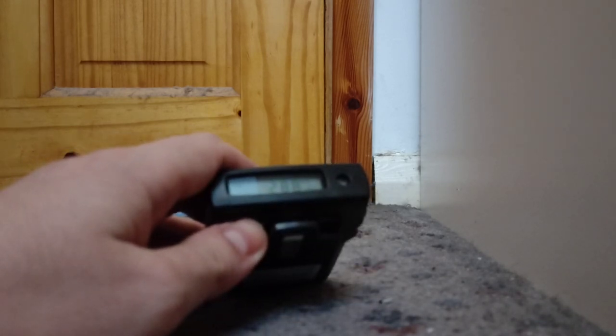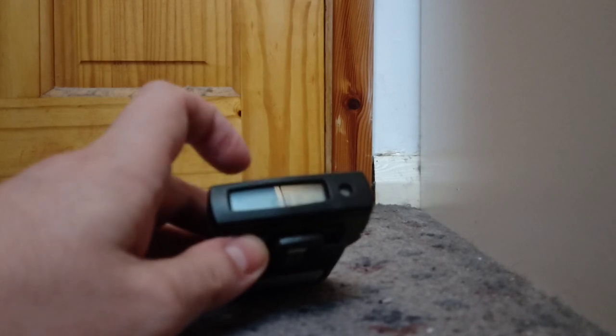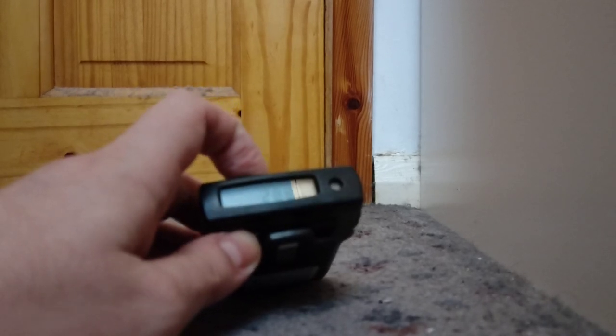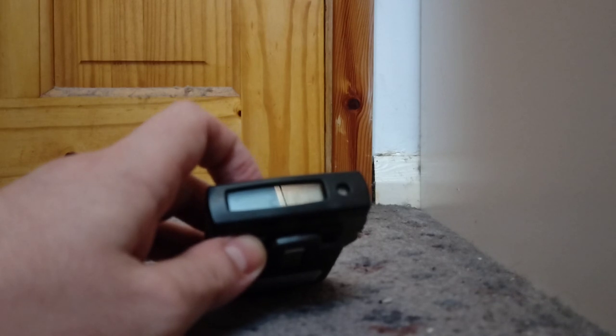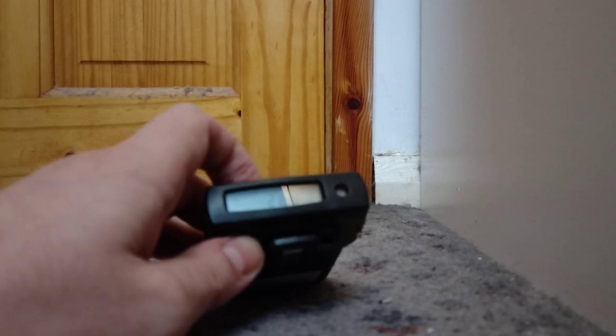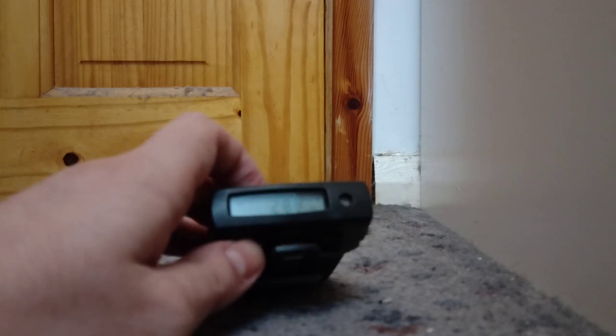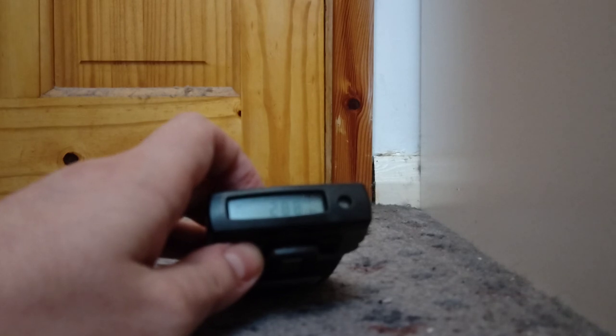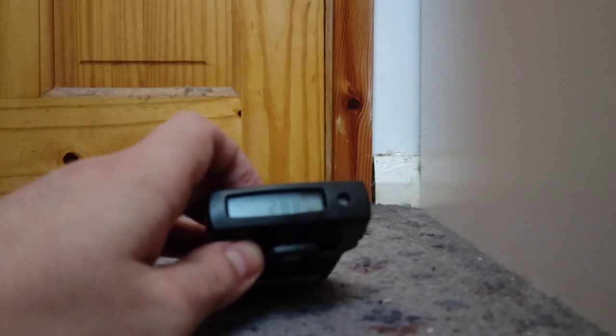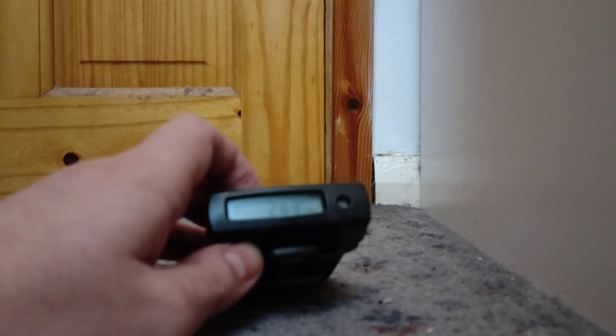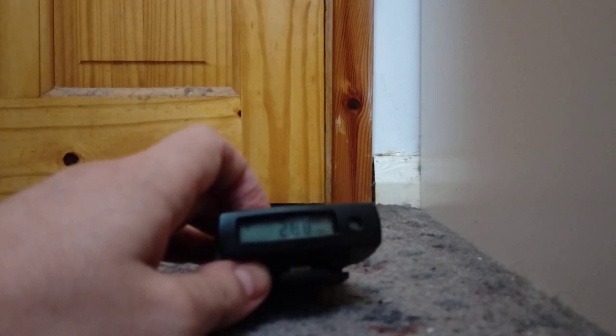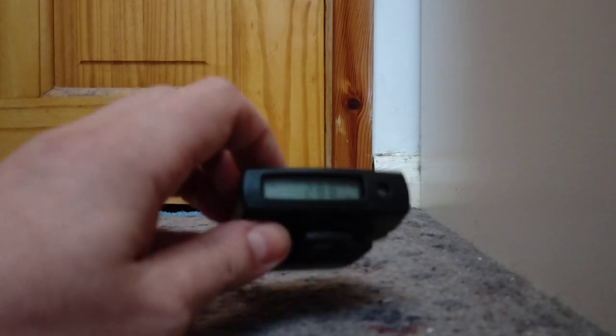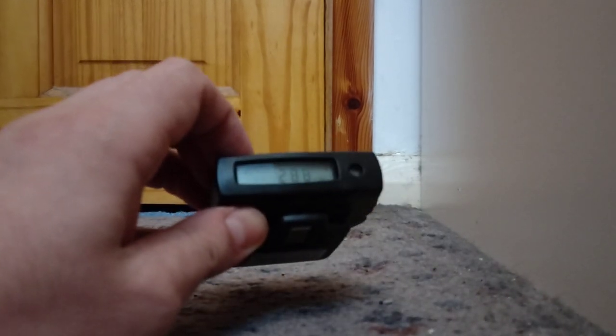So for a lot of people they'd be pretty impractical. All you can basically do on this unit yourself is adjust the alarm thresholds and change a kind of dose equivalence thing. There's one I think is called H10 and the other is called H07. Essentially it's a dose multiplier, so H10 does a 1-1 dose and H07 is a 70% dose. It's designed so if you knew what you were working with in terms of radiation sources, you can more accurately set this to reflect the radiation.